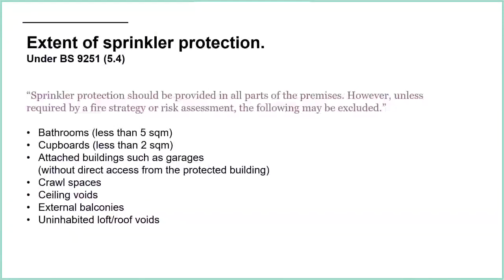The list of areas that may be excluded includes: bathrooms less than five square metres, small cupboards less than two square metres, attached buildings such as garages - but only those without direct access from the protected building - crawl spaces, ceiling voids, external balconies, and uninhabited loft or roof voids. Basically these are areas where we're not expecting a fire to start because they are generally unoccupied and there's not a lot in there.